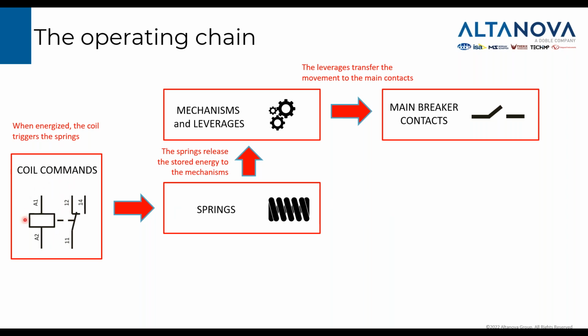Coil commands are, as the name suggests, the devices that trigger the operation. So the coil command will trigger the springs. The springs contain all the energy that will be released to the mechanisms that open and close the main contact through mechanical leverages.